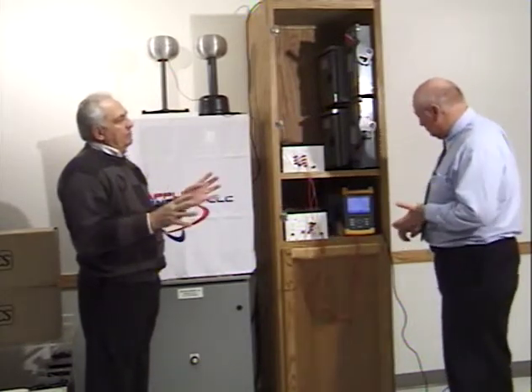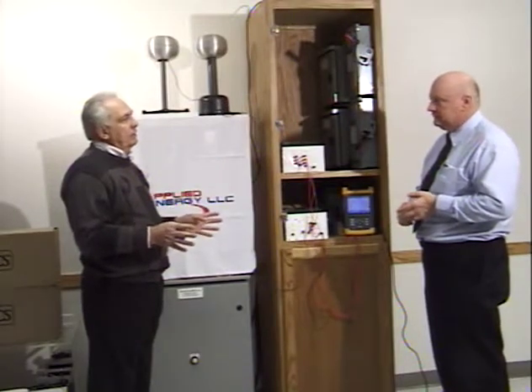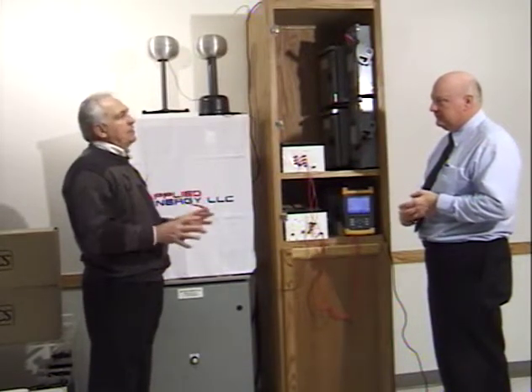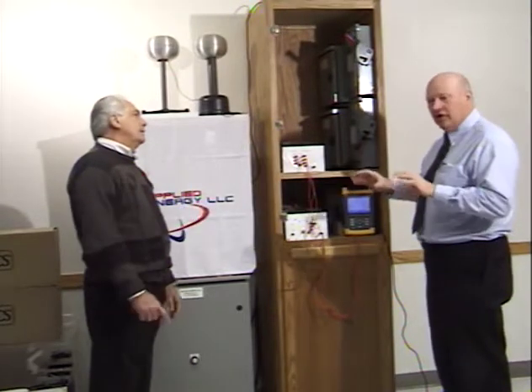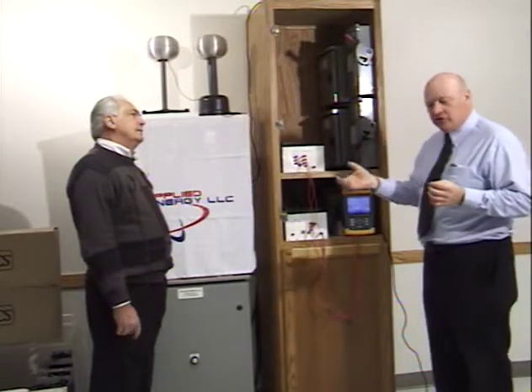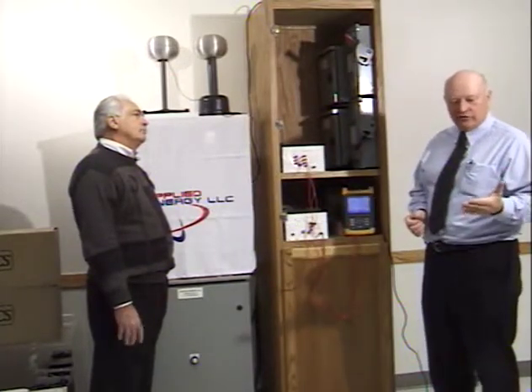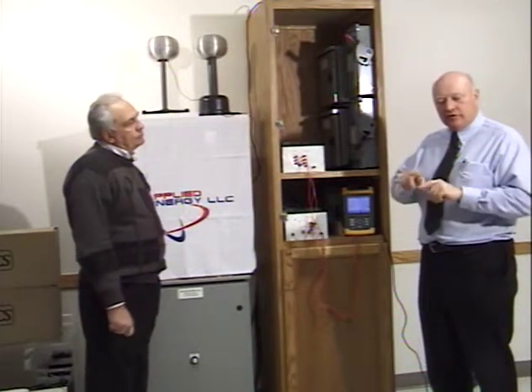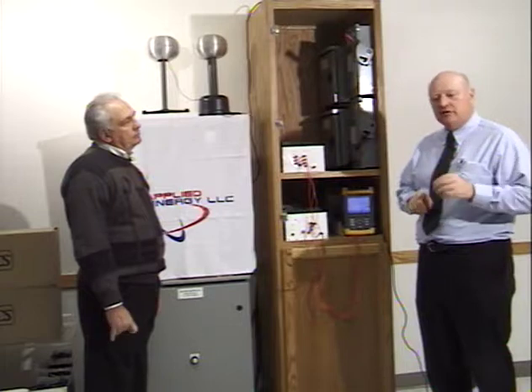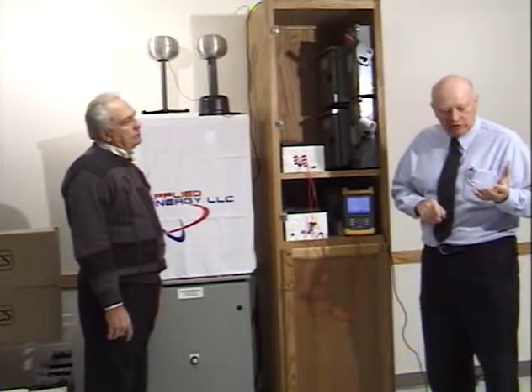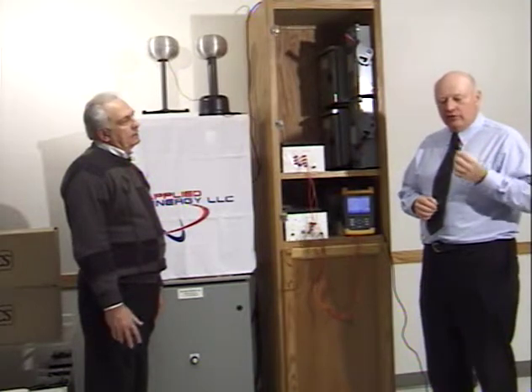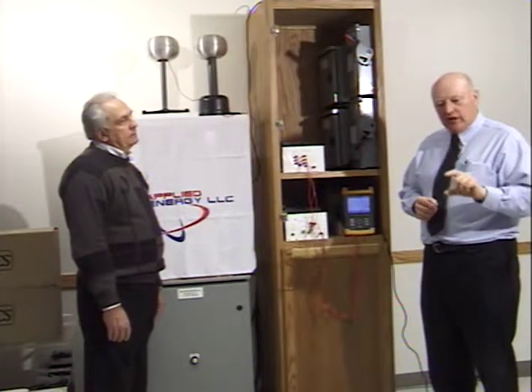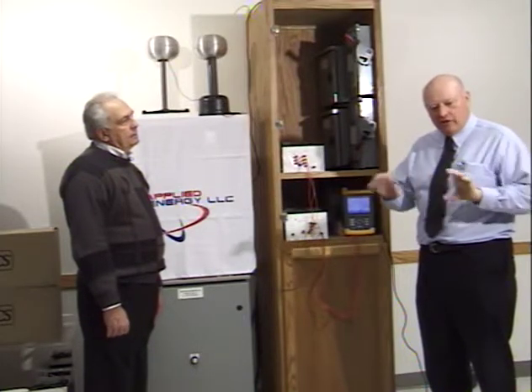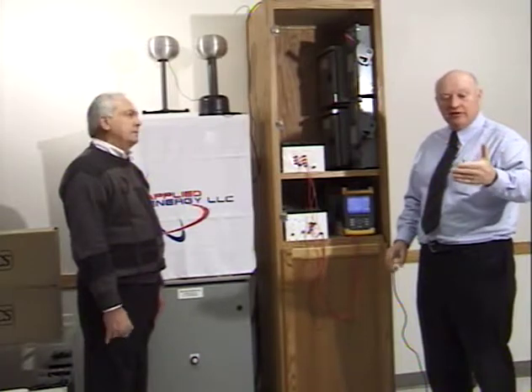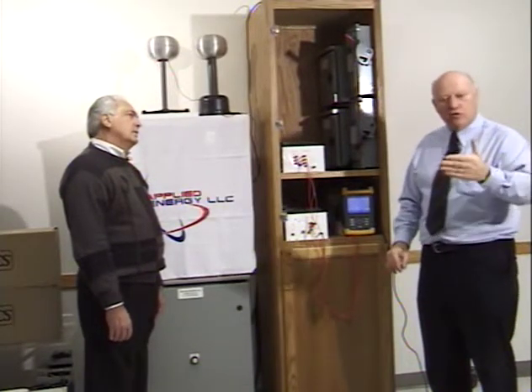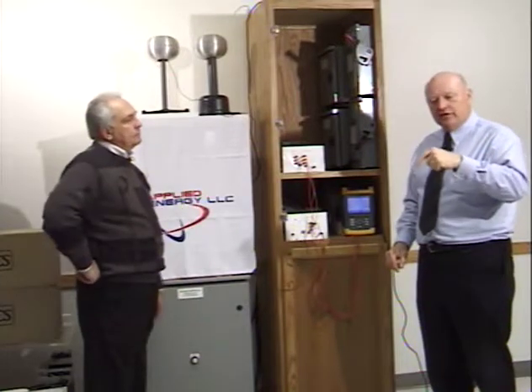Now, by stabilizing this waveform distortion that we have there, what effect does that have on the physical insulation between your drive and motor? The insulation on the wire, the insulation in the motor, and in fact the drive output transistors are all protected because the high voltage spikes, the transient voltage spikes caused by switching transients when the transistors are turned on and off, those switching transients shorten the life of the motor, shorten the life of the wire itself, the cable, shorten the life actually of the devices, the IGBTs or transistor output that is actually making the noise.